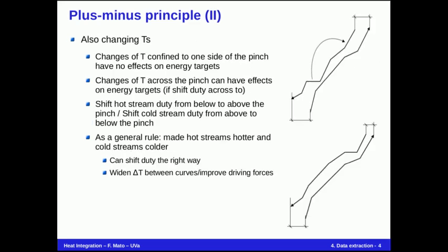This can be done also by changing temperatures, but this change must be across the pinch. Changes of operating temperature limited to one side of the pinch have no effect on energy targets. A change in temperature has effect on energy target only if it shifts duties across the pinch. It is shift hot stream duty from below to above the pinch, or shift cold stream duty from above to below the pinch.